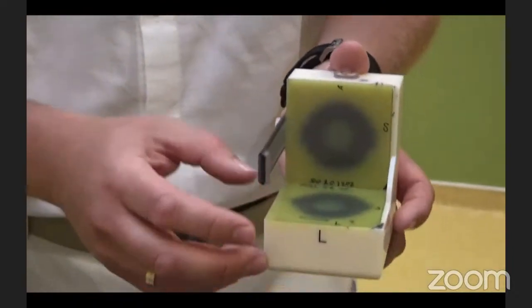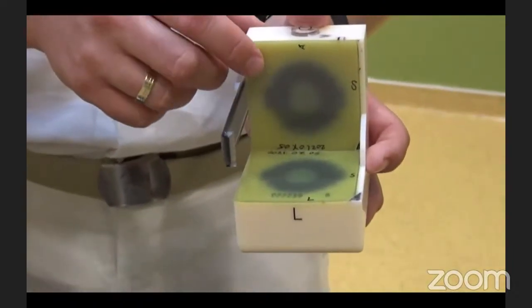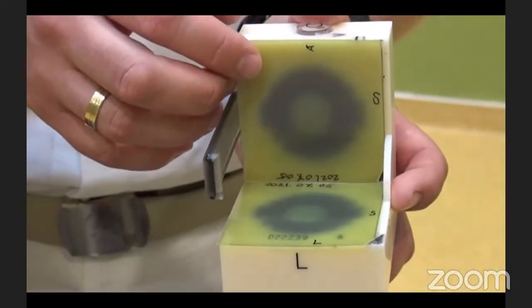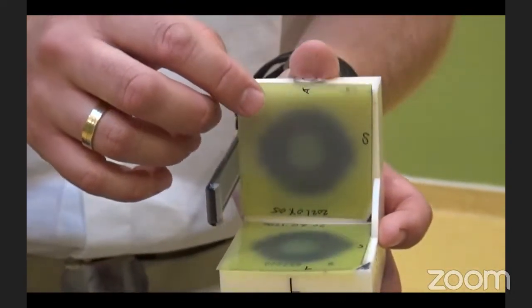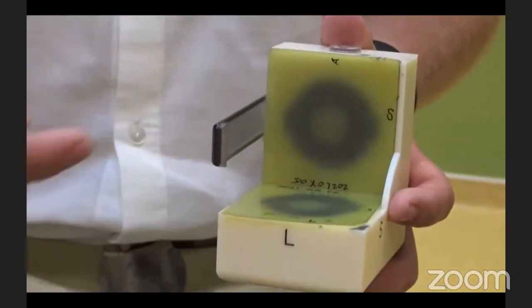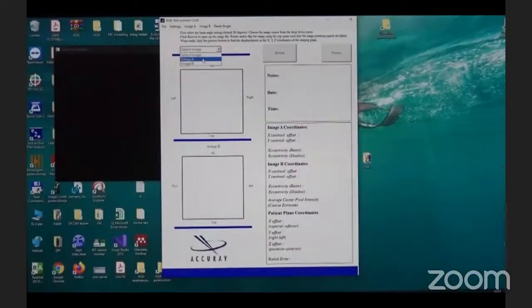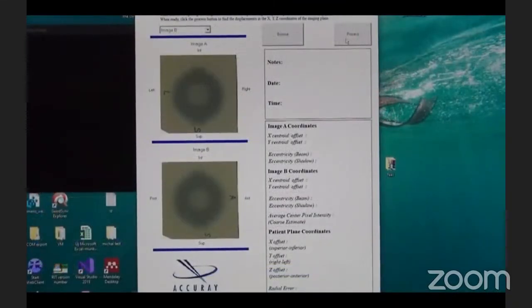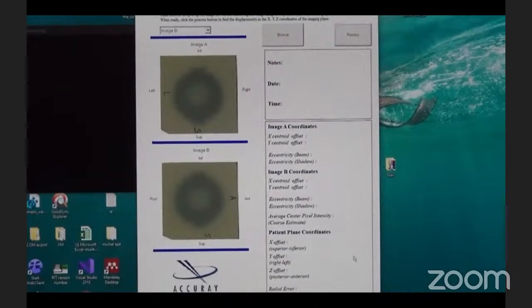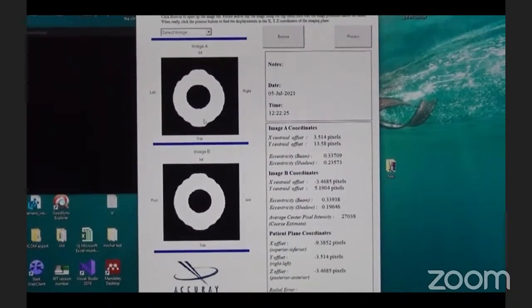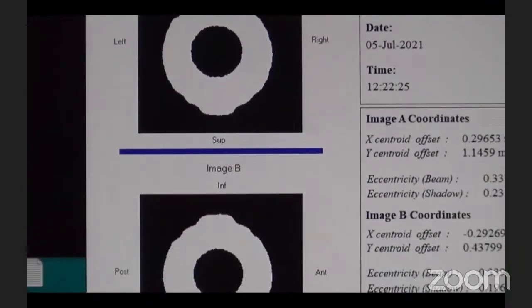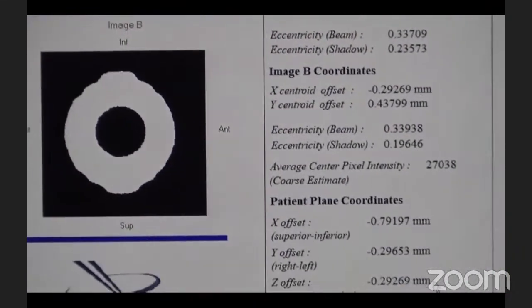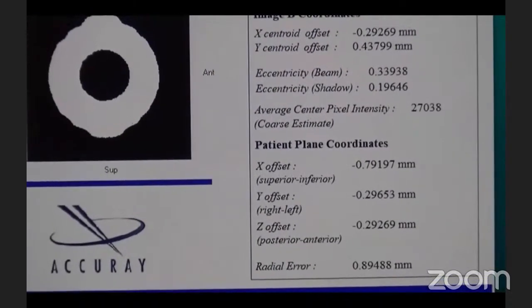And we measure how exactly the ball can be hit in the middle of the circle field from both directions, both anterior and lateral. For AQA tests, we load the 2 images, and then with the software we evaluate the targeting precision, and we can see the total radial error is 0.9 mm, which is below tolerance.